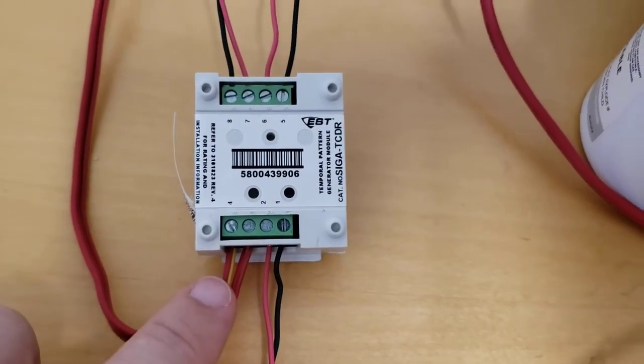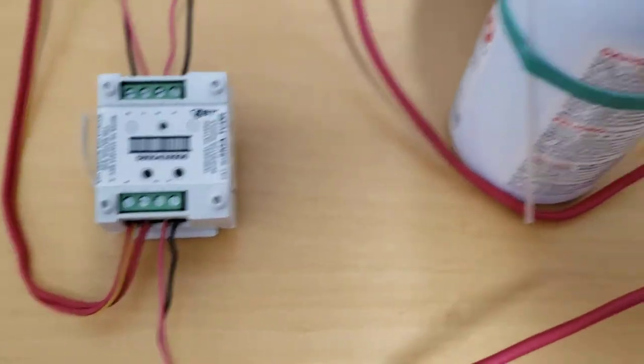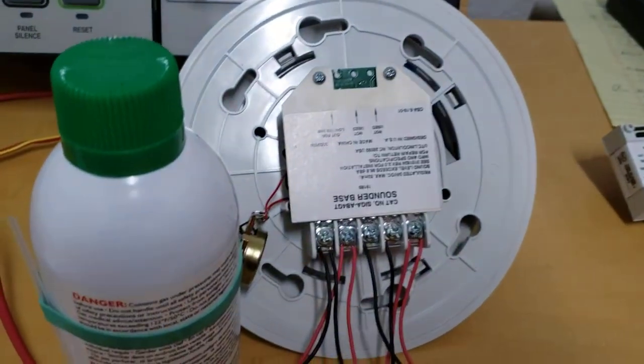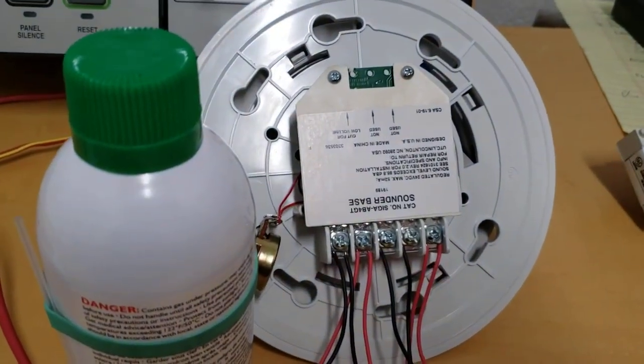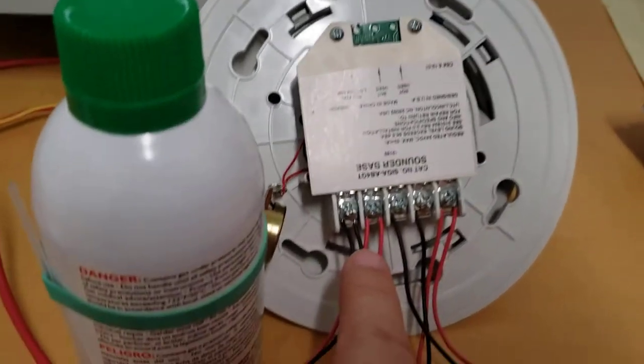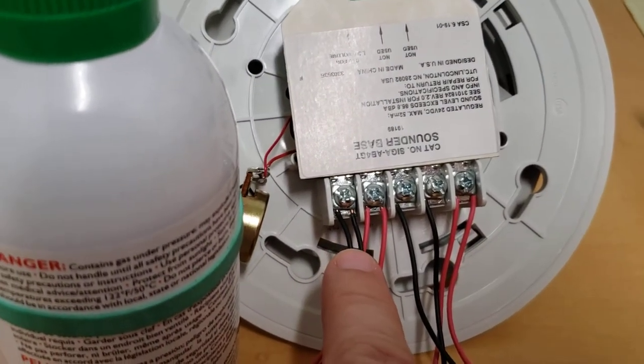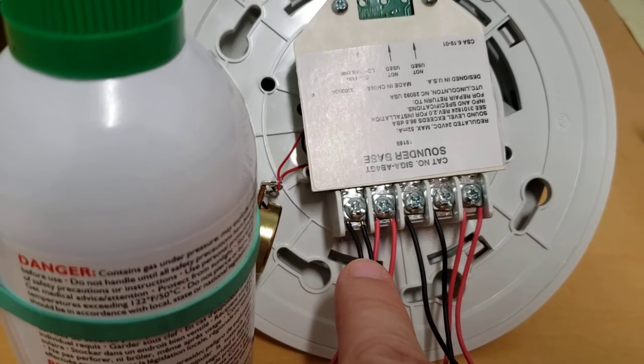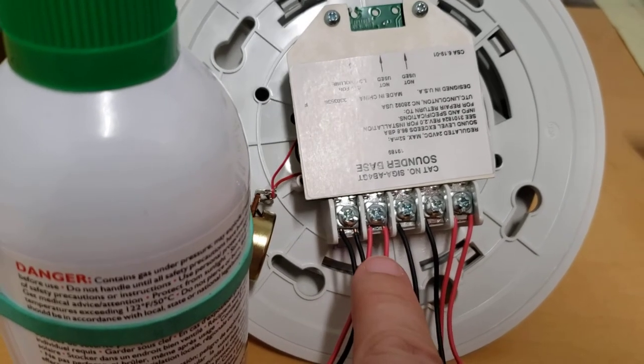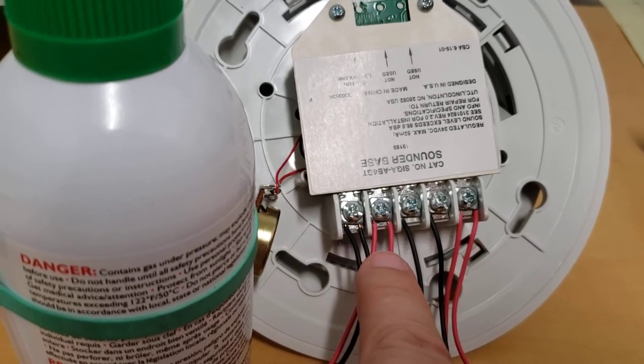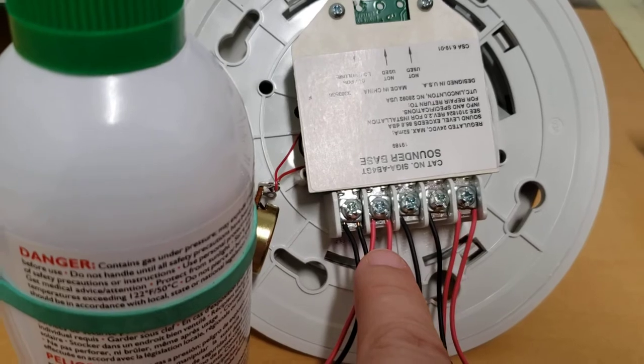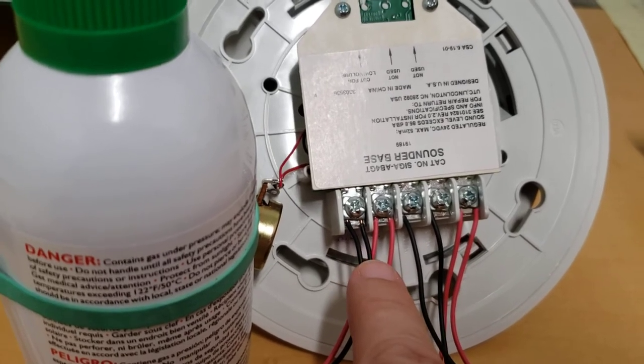This is the SLC wiring standard. Here's a SIGA AB4 GT. It is also wired correct even though its black wires are going to the terminal labeled SIG positive and the red wires are going to the terminals labeled SIG negative. That's the correct wiring.